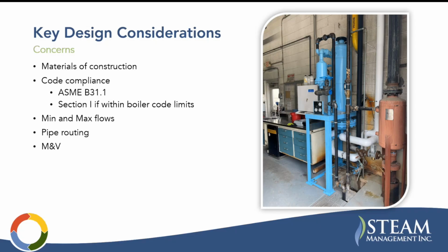And then M&V: how are you going to measure the performance of the system? I would say that we often see this as a sub-measure of an overall steam plant optimization measure, where they're using Option C to evaluate boiler plant fuel consumption before and after implementation. And they're pairing this with maybe other boiler plant upgrades like an O2 trim system on a burner, or maybe a new boiler altogether, or optimizing a deaerator, or boiler plant pressure reduction, or whatever the different measures are, and they bundle them together as an overall steam plant optimization measure.